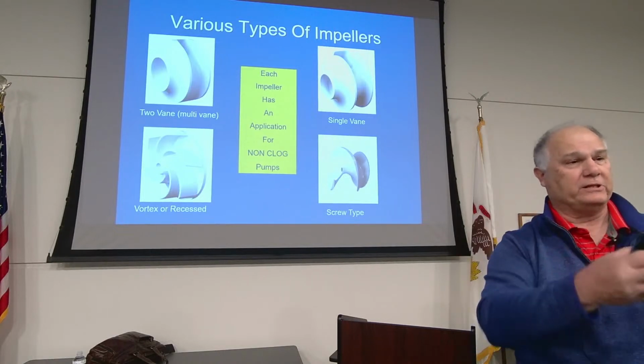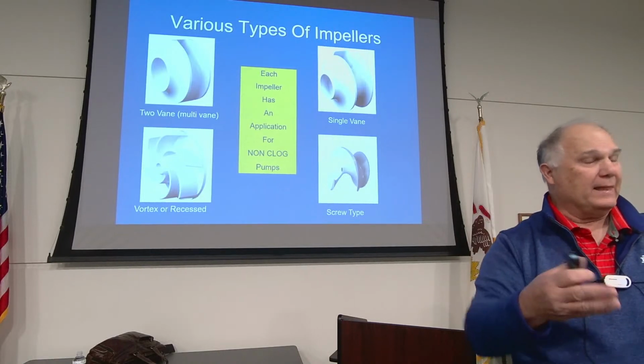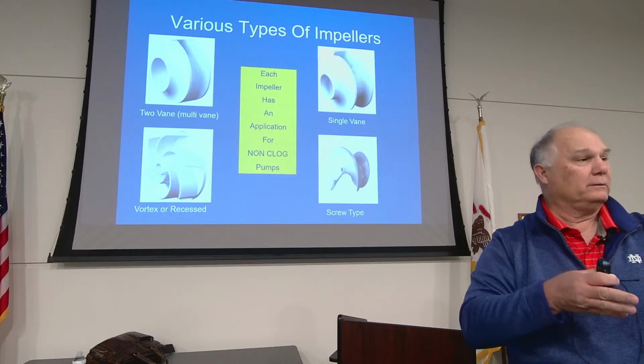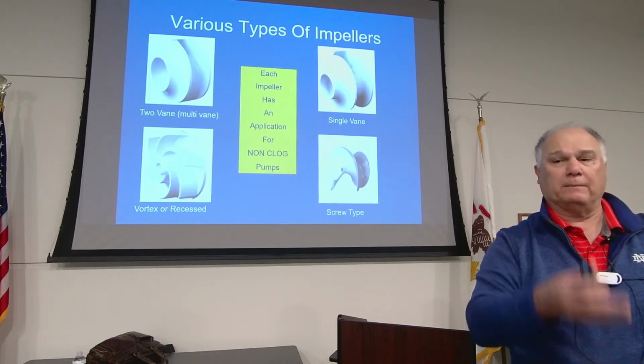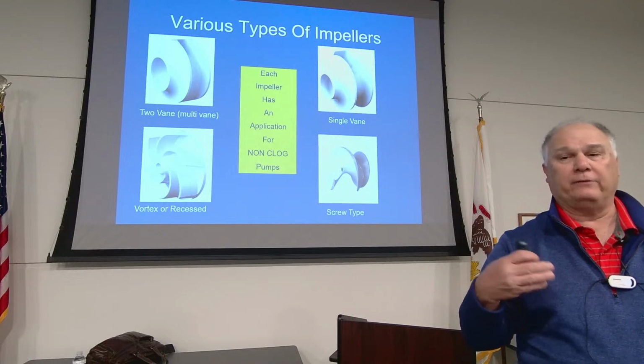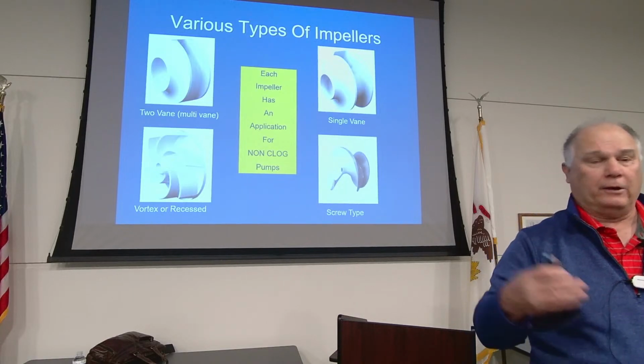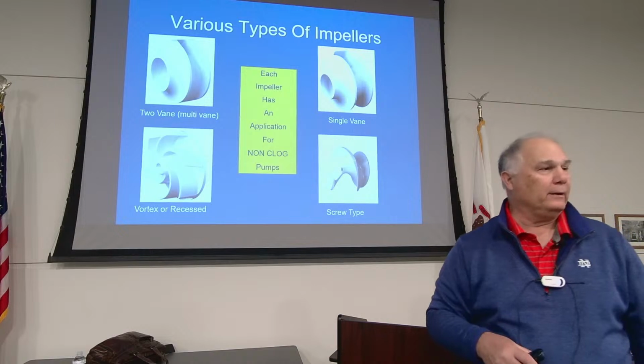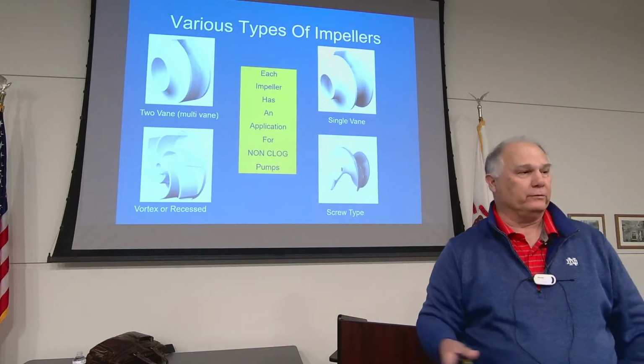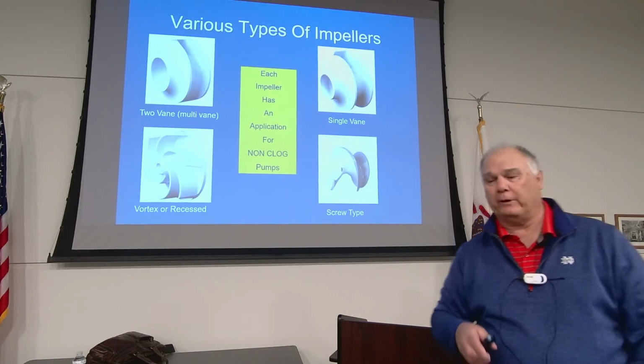You take 360 divided by 5. That's less than 90 degrees apart. That rag is going to come up, get stuck in between 2 vanes, and plug that pump. At 180 degrees, there's less of a chance of doing that. With a vortex, there's no chance of doing that, because there's no vane that we really worry about.